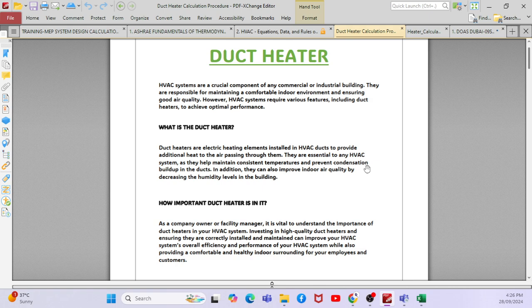That is something you have to discuss with your manufacturers and select with the manufacturer, to try to make a balance. Normally, we will propose one option with a double heat wheel, then one with preheat and pre-cool coil, the horseshoe pipe, and another option with a duct heater. We will see whichever uses lesser power. Ultimately the double heat wheel will use the least power. But where you cannot achieve the condition, you will go with the pre-cool or preheat pipe, and the duct heater as a third option.